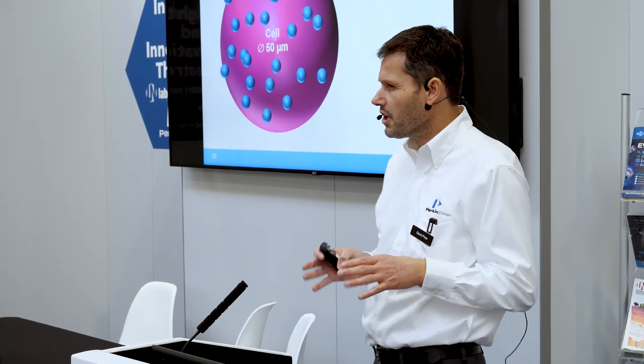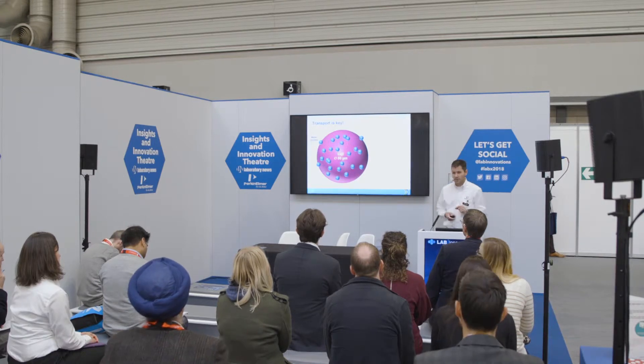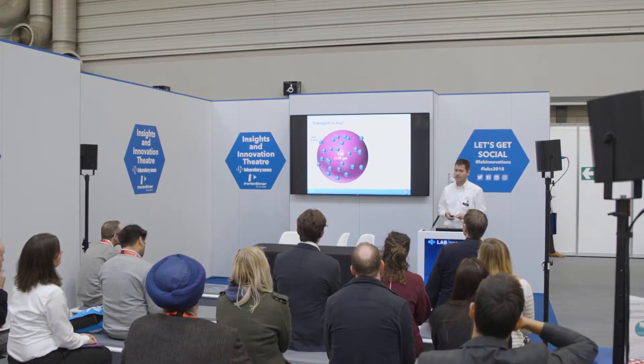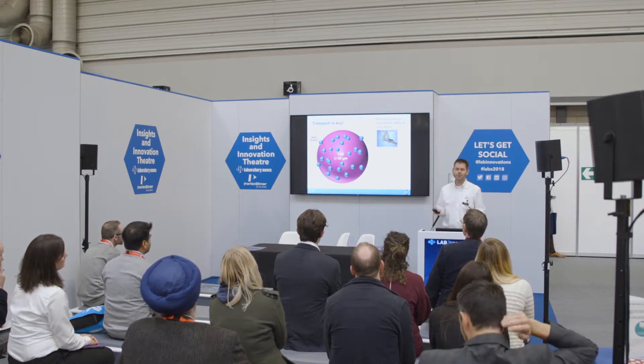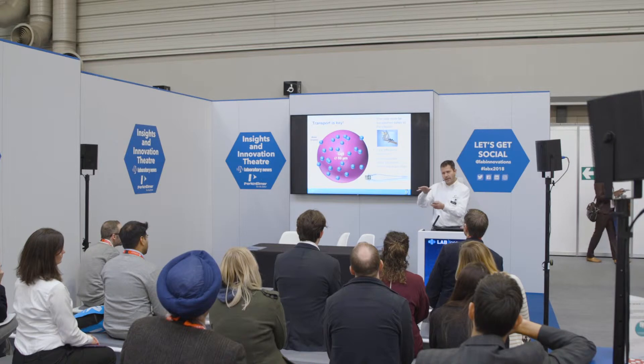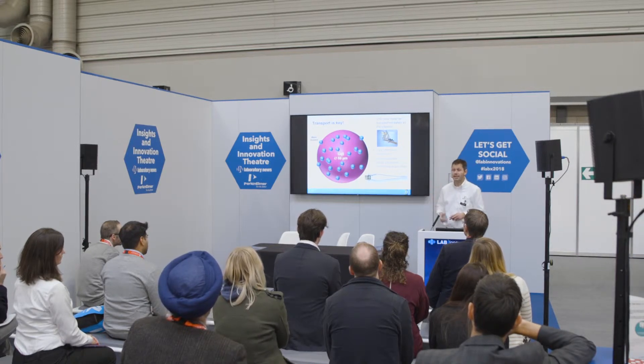Looking after cells is critical. Cells can be around 50 microns across, whereas the water droplets normally analyzed with ICP-MS are tiny. The analogy is getting Dumbo to fly — he's a big guy but he can do it. We use a high-efficiency nebulizer and a special spray chamber: we spray the sample in, add argon around the outside of the spray chamber to ensure cells don't bump into the sides and lyse before reaching the plasma.